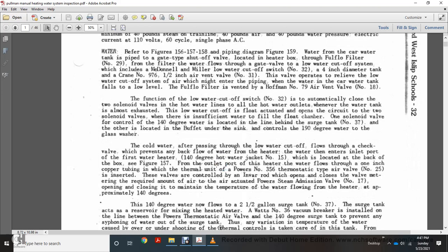The function of the low water cutoff switch number 32 is to automatically close the two solenoid valves on the hot water lines whenever the water tank is almost exhausted. When the low water cutoff opens the circuit, the two solenoid valves close: one solenoid valve controlling the 140-degree water is located in line behind the surge tank number 37, and the other is located under the sink controlling the 190-degree water to the glass washer.